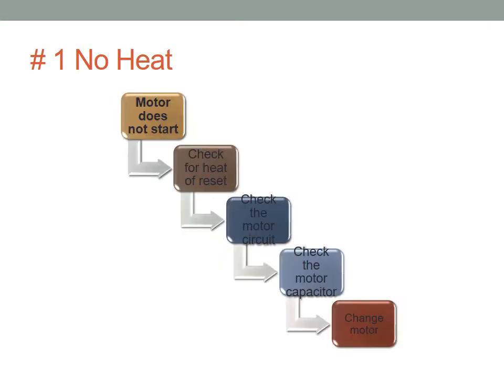Again, no heat. Motor does not start. Check and reset the motor. So there's nothing in the motor at all. It's not functioning, so we'll check the motor, reset, check the circuit, make sure again it's getting 120 volts. A lot of times we have voltage but not enough voltage, something went wrong. Check the motor capacitor if it has one. If you have a split phase plug, it has a capacitor, so make sure we have the right capacitor. If all of this checks out and the motor is still not running, probably something is wrong with the winding, probably it's burnt. Change the motor.